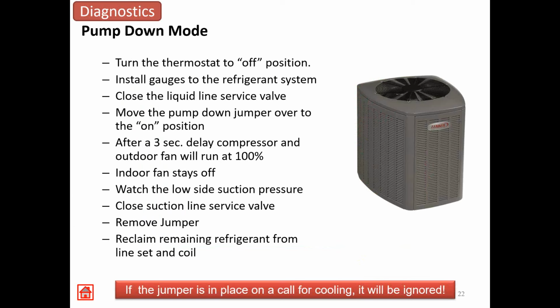You move the jumper over. There's 3 seconds of delay on it, the compressor will start and the fan will start 100%. Indoor fan stays off, and then you're going to suck it down until it gets about 20 psi, and then remove the jumper, reclaim the remaining amount of refrigerant.